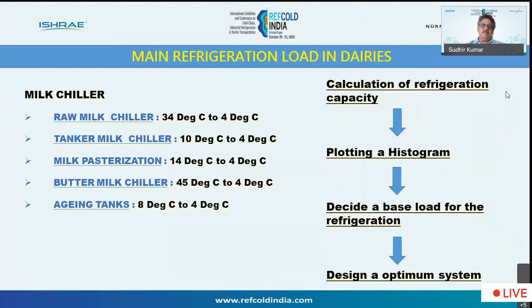Pasteurization of the milk happens. Basically, milk is heated up to 80 degrees, and after that, it is regenerated. And then after regeneration, we use chilled water, which is basically cooling it from 14 degrees to 4 degrees. Again, buttermilk is also cooled from 45 to 4 degrees, and in aging tanks we maintain the temperature at 4 degrees. So basically, to calculate this load, because you need to calculate the total load required per day, you need to plot a histogram to design the optimum system and the base load of the system.